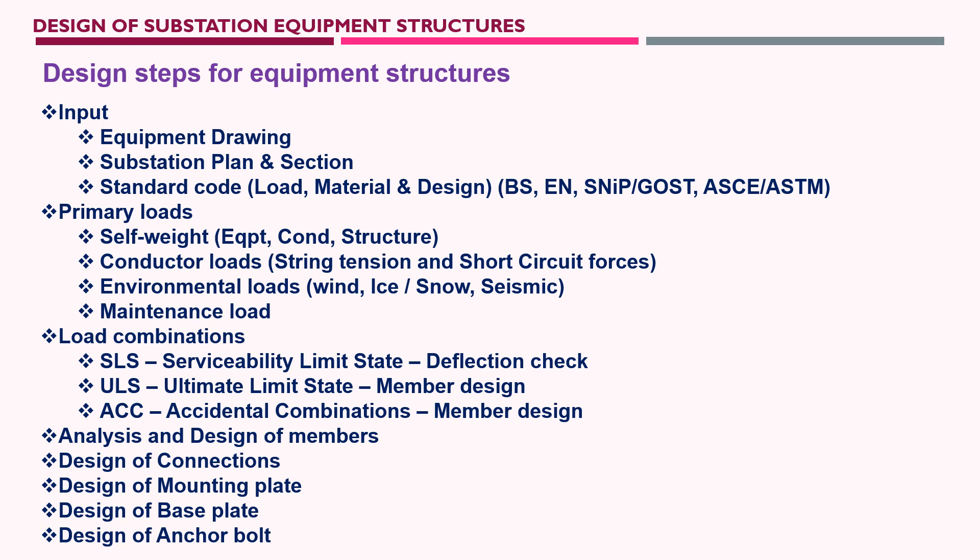For primary loads, the self-weight of equipment, conductor, and structure must be considered. Conductor loads are electromechanical loads — conductor string tension and short-circuit forces — calculated by the electromechanical engineer. Environmental loads include wind, ice, snow, seismic, temperature, and fire as required by project specification. Maintenance loads account for a maintenance engineer climbing the structure, typically 150 kg (1.5 kN) or 100 kg (1 kN) as per standard codes and project technical specifications.